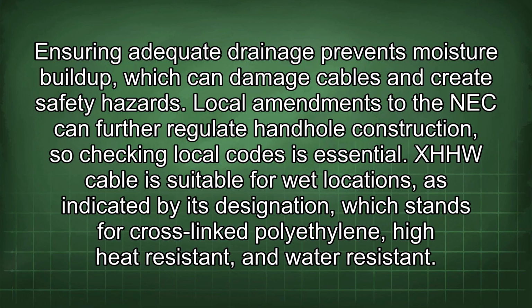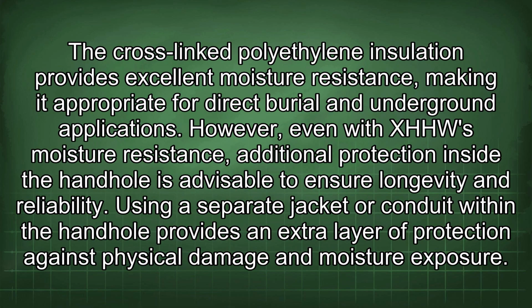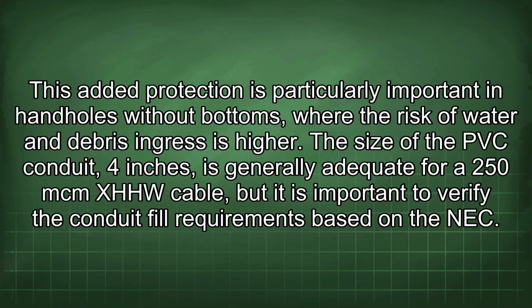Local amendments to the NEC can further regulate handhole construction, so checking local codes is essential. XHHW cable is suitable for wet locations, as indicated by its designation, which stands for cross-linked polyethylene, high heat resistant and water resistant. The cross-linked polyethylene insulation provides excellent moisture resistance, making it appropriate for direct burial and underground applications. However, even with XHHW's moisture resistance, additional protection inside the handhole is advisable to ensure longevity and reliability. Using a separate jacket or conduit within the handhole provides an extra layer of protection against physical damage and moisture exposure. This added protection is particularly important in handholes without bottoms, where the risk of water and debris ingress is higher.